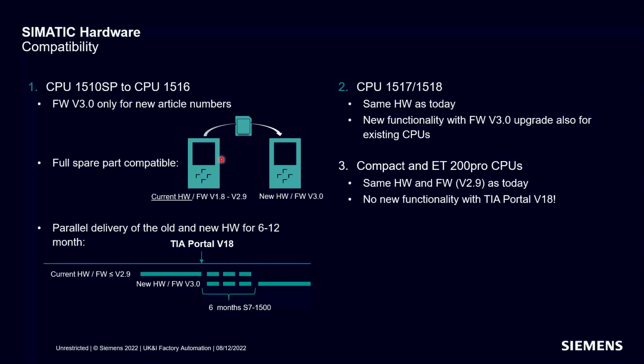It's just memory card out of the old one into the new one. Granted, the new CPU will run faster, but it's what we class as spare part compatible, so no changes required in the application code. That's the same across the board for all the 1500 Pro CPUs, and it doesn't matter what firmware you're on - you can take the memory card from the older unit and drop it into the new unit, and it will run up absolutely beautifully.